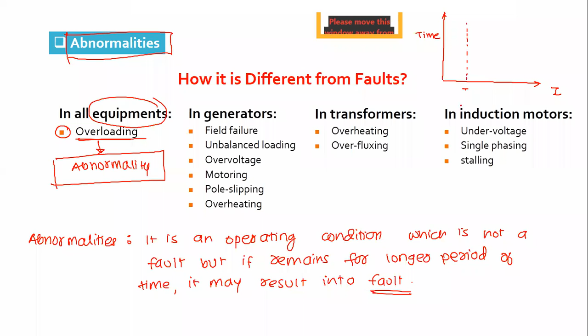Fine. And if I draw the thermal withstand capability curve, which is mainly corresponding to insulation. Now, in case of motor, what will happen? It can take the full load for any period of time. As you can see from the characteristic, there is no time limit for which the motor can work on the full load current. But for example, you have overloaded the motor by some percentage. Now the motor will draw more current from the supply, and as the current is more than the rated capacity, more than the continuous maximum rating, CMR, this current will cause additional heat generation in the winding, and that will overheat the insulation. The insulation can withstand this overheat, as per the design of the insulation, for this much period of time.